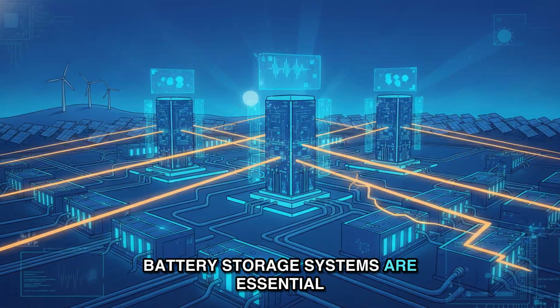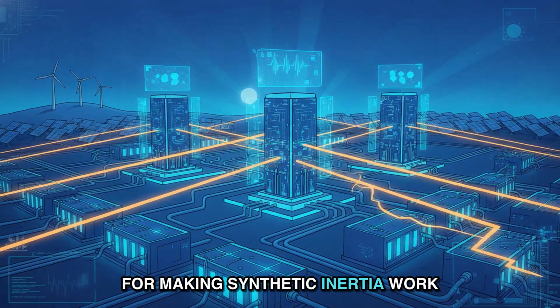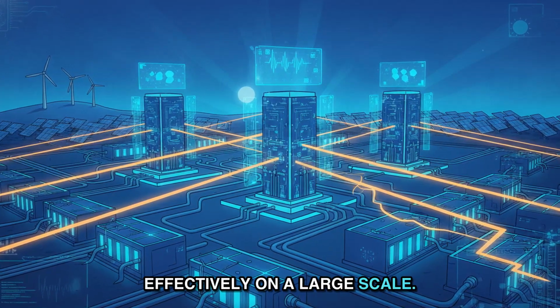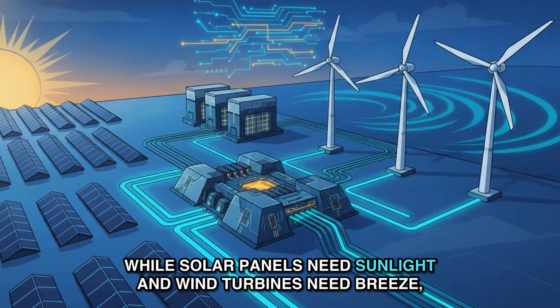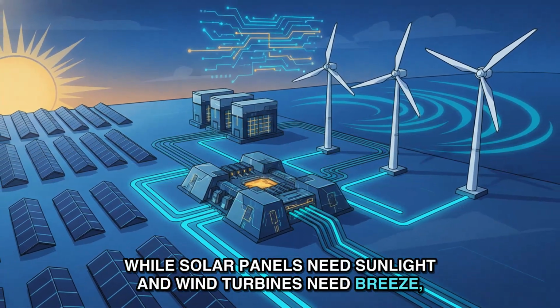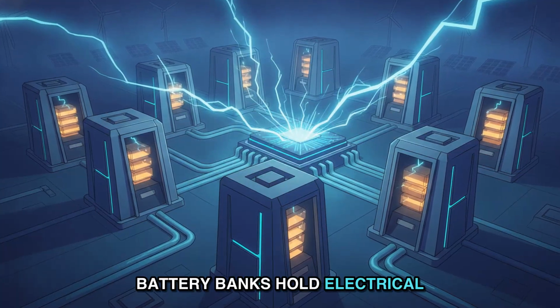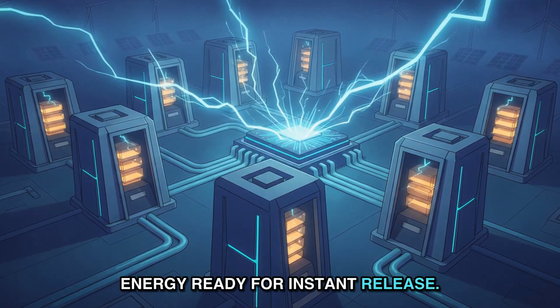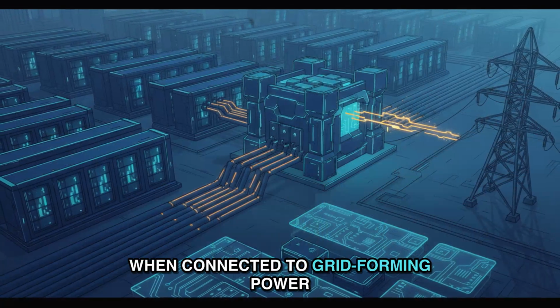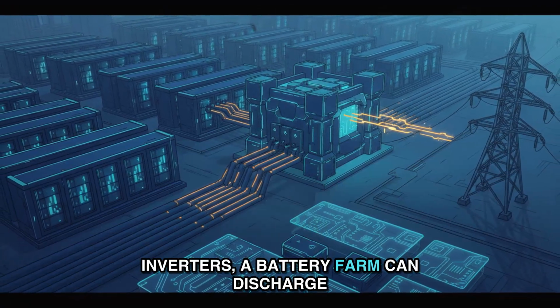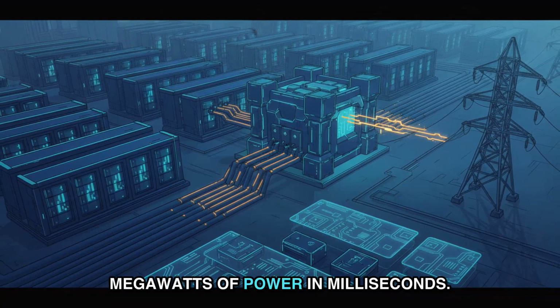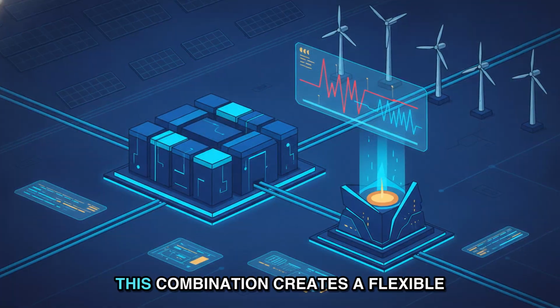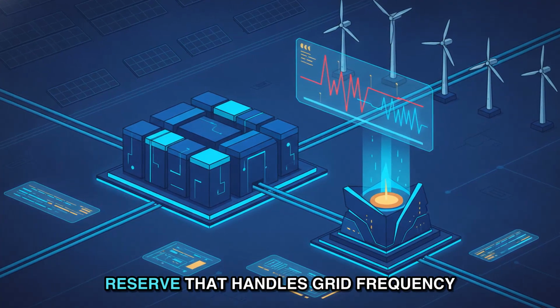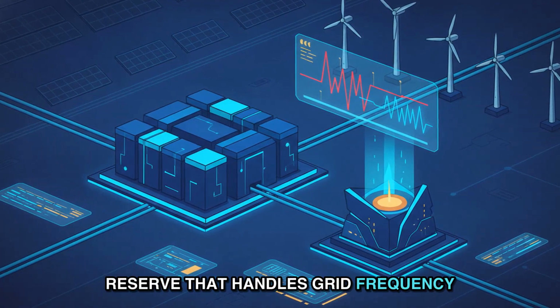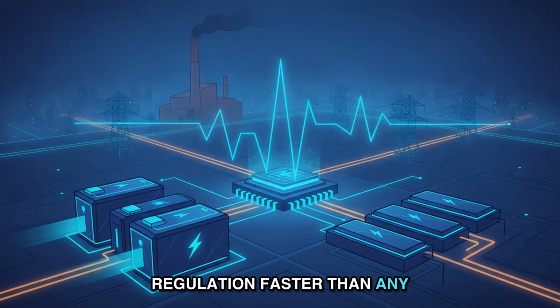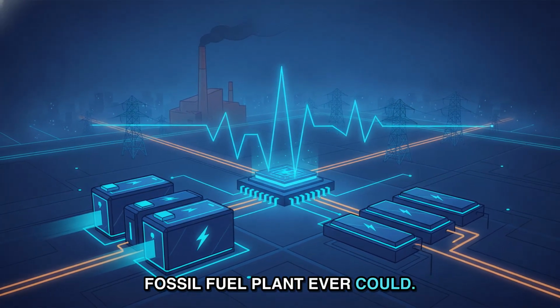Battery storage systems are essential for making synthetic inertia work effectively on a large scale. While solar panels need sunlight and wind turbines need breeze, battery banks hold electrical energy ready for instant release. When connected to grid-forming power inverters, a battery farm can discharge megawatts of power in milliseconds. This combination creates a flexible reserve that handles grid frequency regulation faster than any fossil fuel plant ever could.